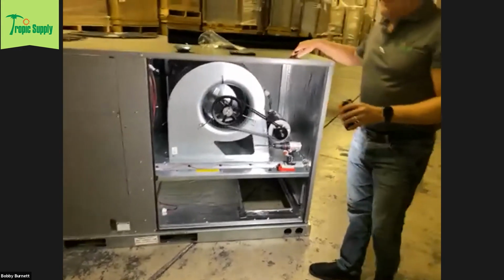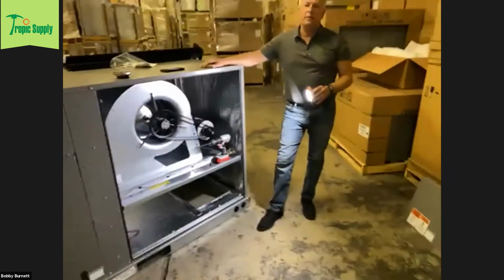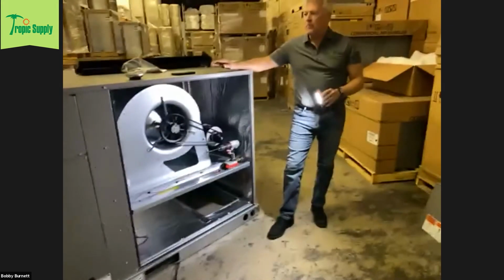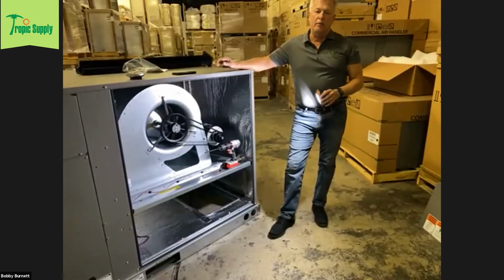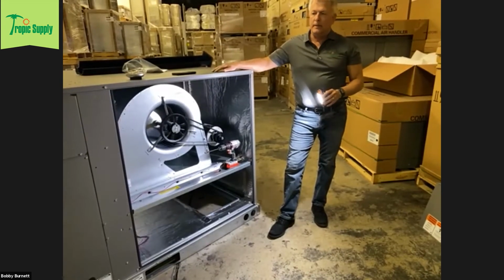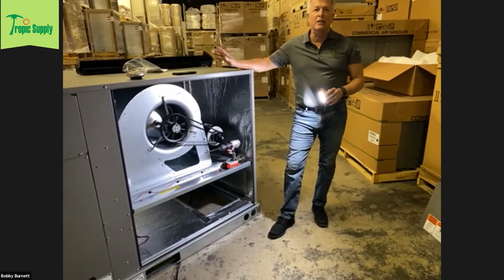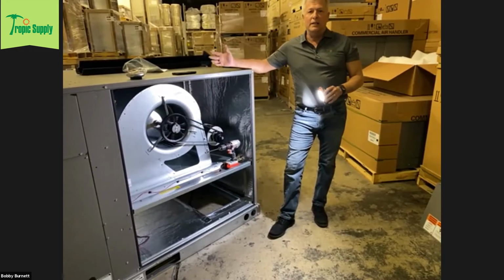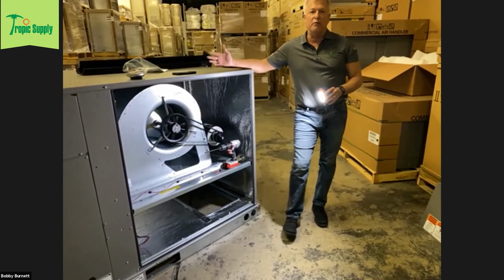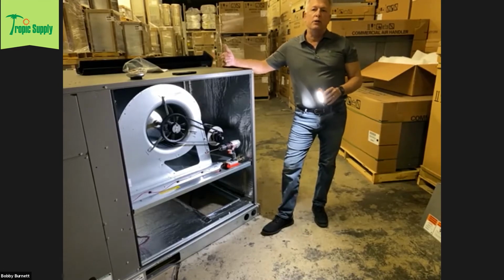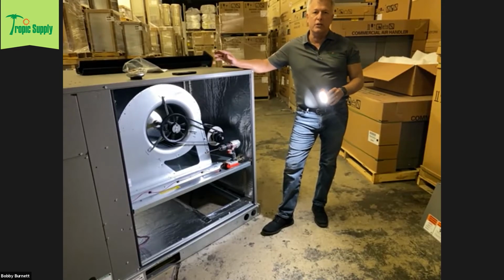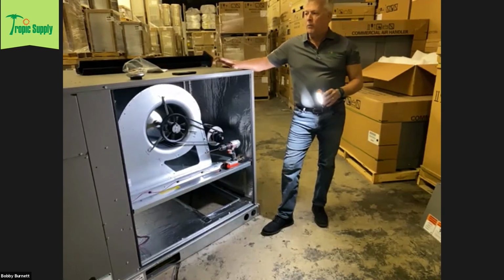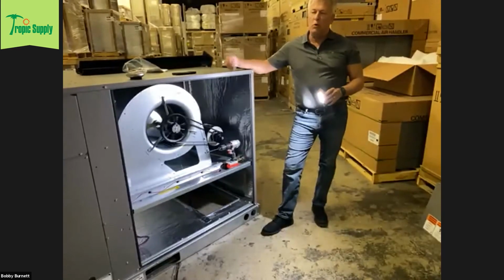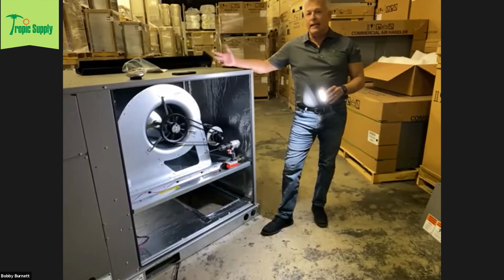One of the things they've done with these new units is change the footprint to match what they'd call the most common industry standard. What I'm telling you is it's pretty much matched up to your Carrier footprint. So your Carrier, Bryant, and ICP commercial products out there, one of the most common footprints in the industry, they've matched that. So you won't need a curb adapter if you're adapting to any of those.